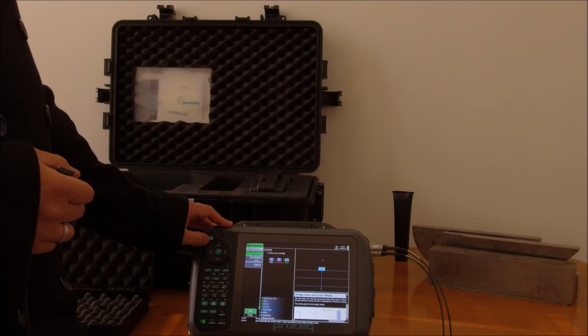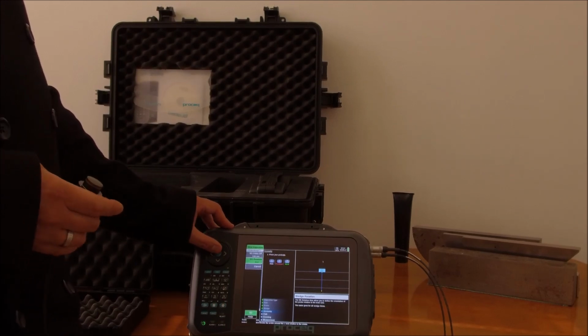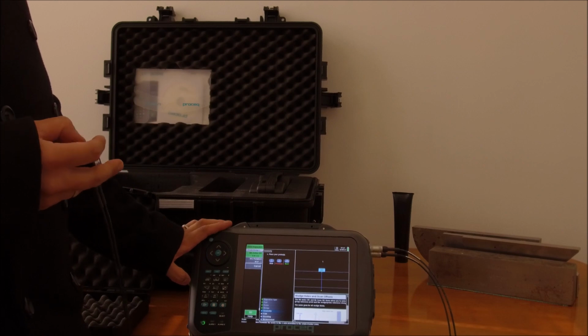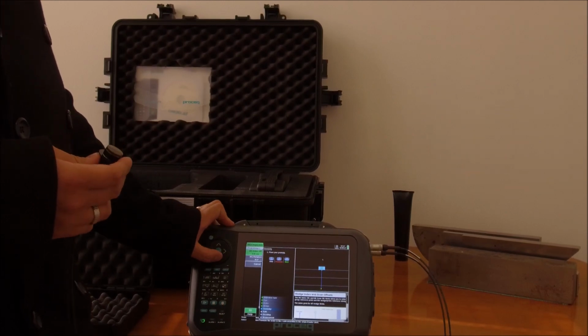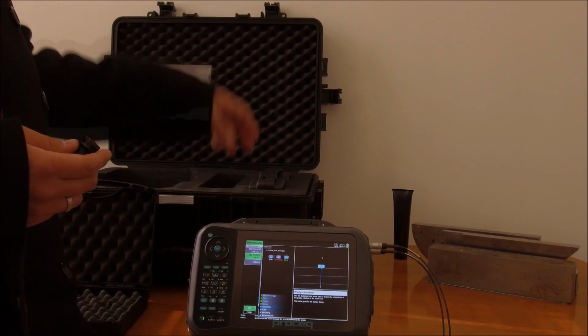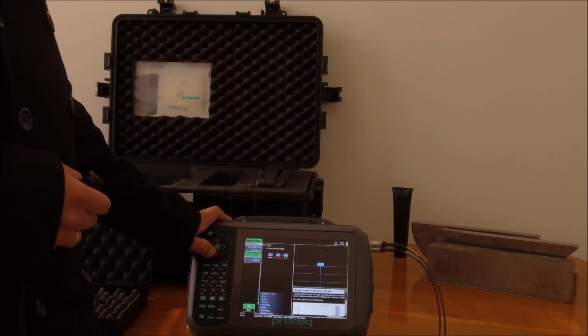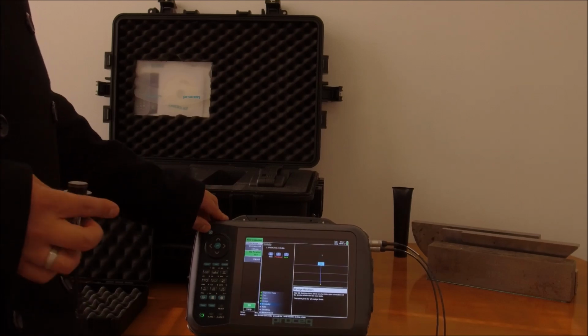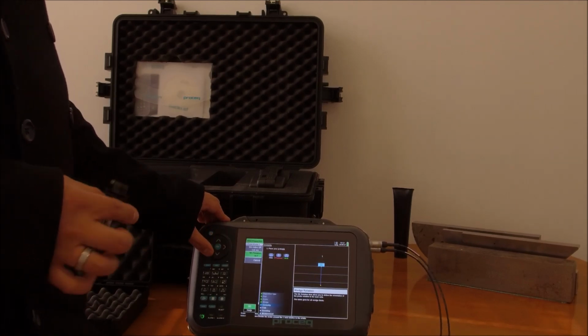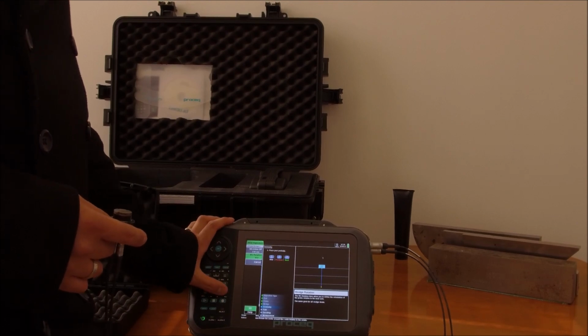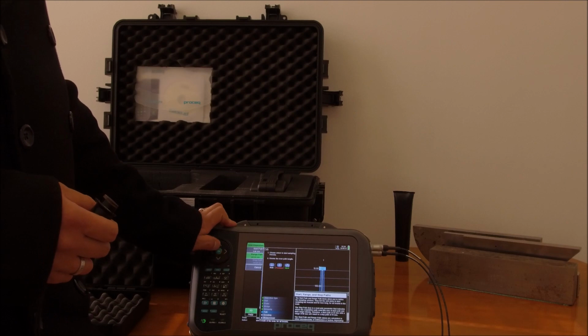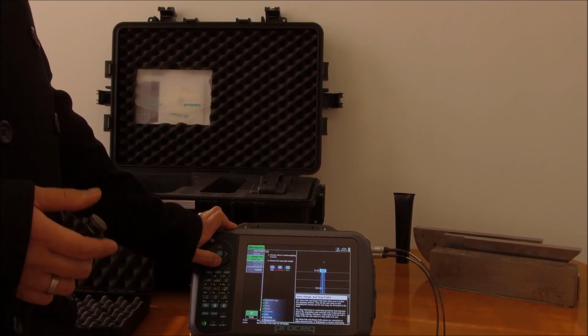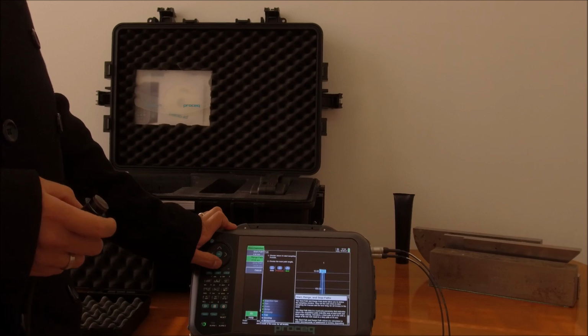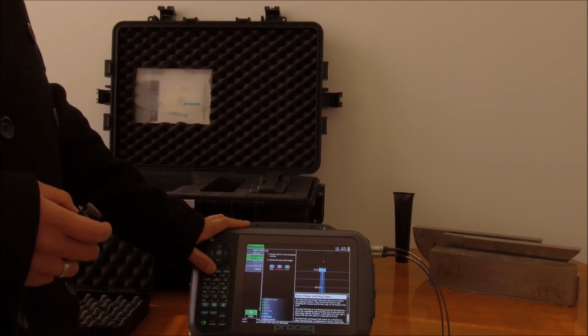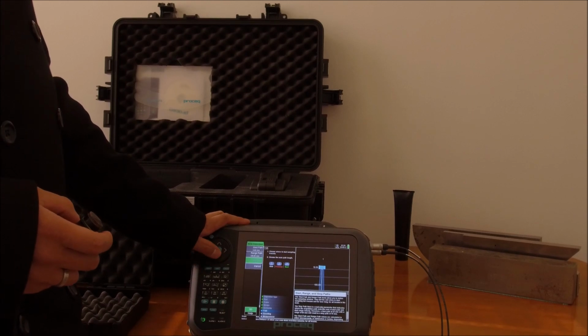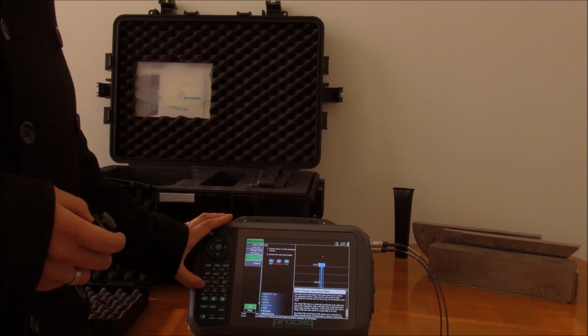Okay, in this next menu here we can nominate the index point. So the index point is where we expect our sound to come out of the probe, and we can nominate our rotation in regards to our scan axis. In this instance it's normal, so we're talking a 0 degree probe, so we're talking 90 degrees to the scan axis. Then we can nominate our range. So because we're going to be playing with a standard test block, I'll just leave it at 100. Okay, so 0 to 100 is what we're going to be working with.